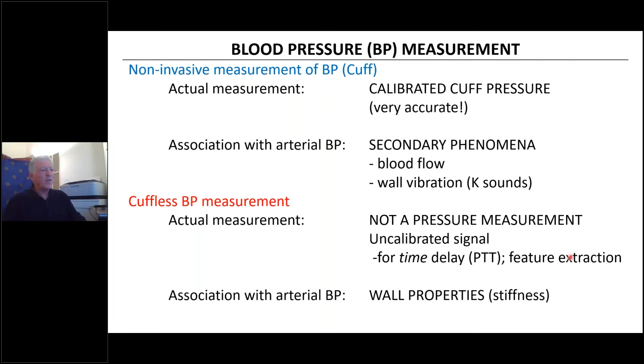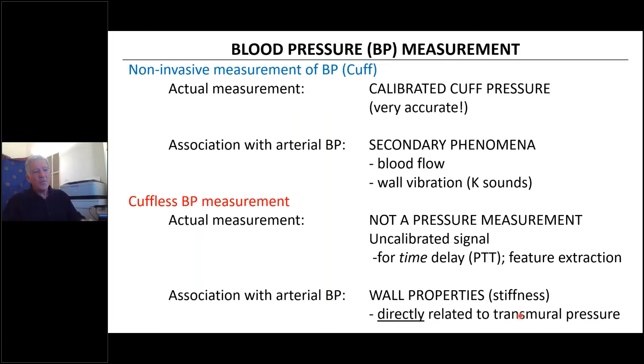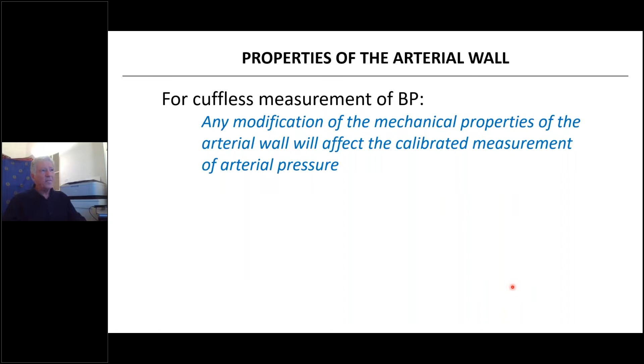In the cuffless measurement, there is no pressure measurement, right? So we have a pressure value with no pressure measurement. That's important to understand. There's no force measurement in these cuffless measurements, other than maybe a transducer that detects the waveform. It is an uncalibrated signal, and it's used essentially for time delays or for feature extraction. And the association is the wall properties, the properties of the arteries, which is the arterial stiffness. And this is directly related to the pressure. So these wall properties are highly relevant in relation to what the transmural pressure is. So for cuffless measurement of blood pressure, we know that any modification of the mechanical properties of the arterial wall will affect the calibrated measurement of arterial pressure.